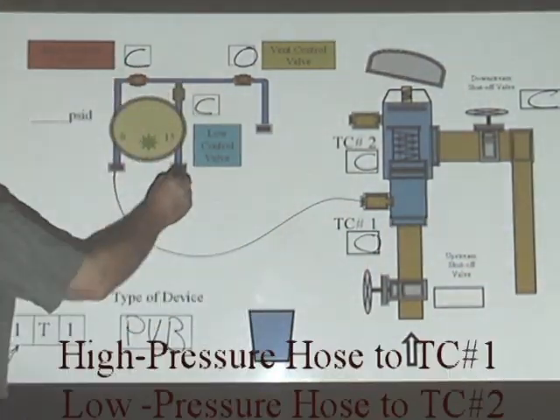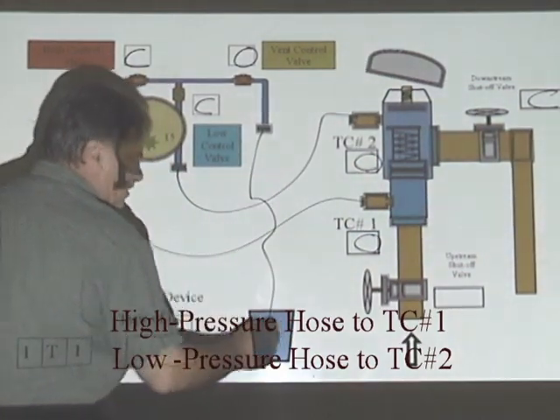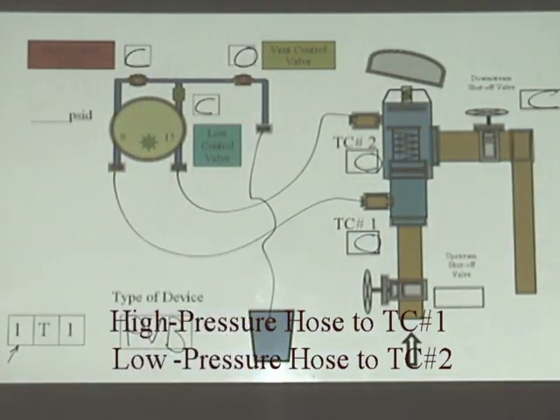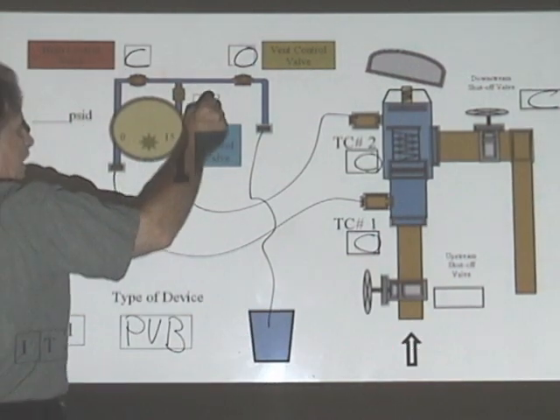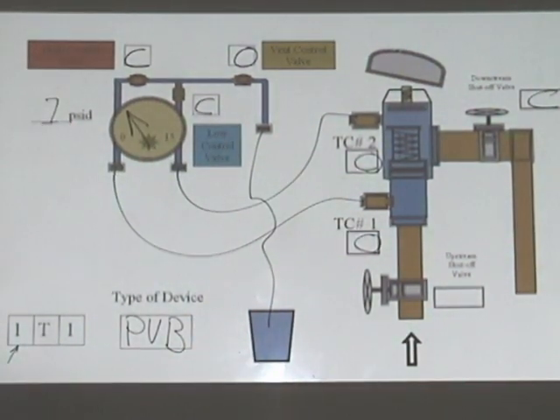high side, low side to number two, open that up, vent in the bucket, bleed my high, bleed my low, take my reading. I should have a differential pressure of one or greater.